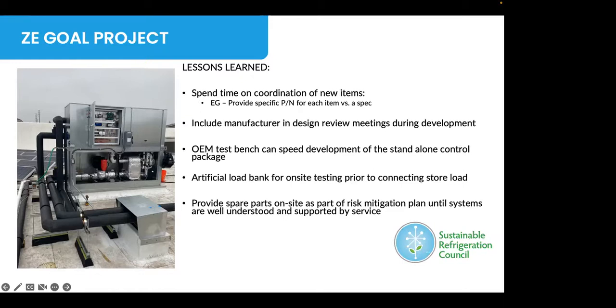We also put an artificial load bank on the chiller so that we could start it up and commission and test it prior to connecting live loads on the store. That's not something you'd necessarily need to do on every project going forward, but for the first several, Walmart wanted to ensure the system started up successfully, and that was huge on this project.